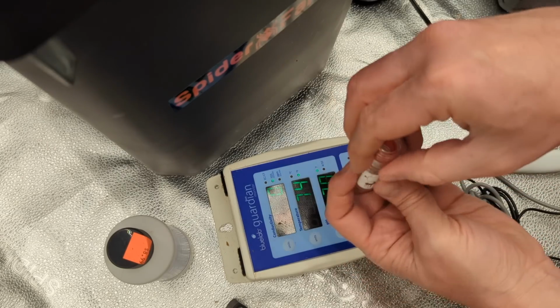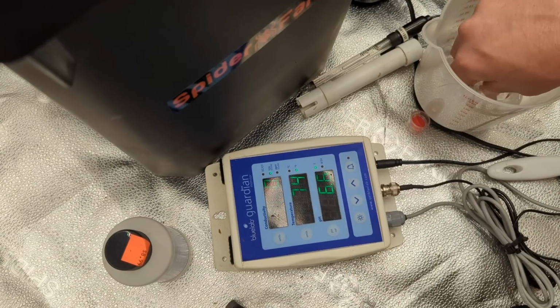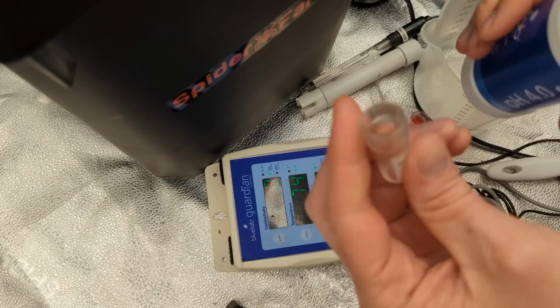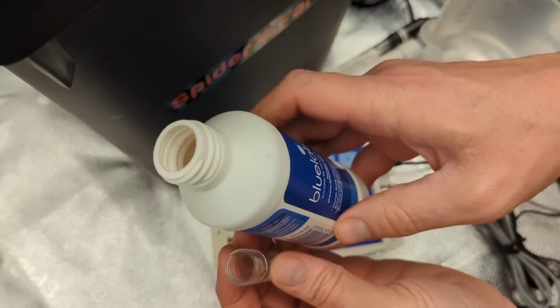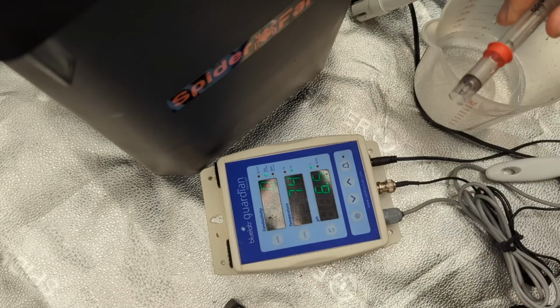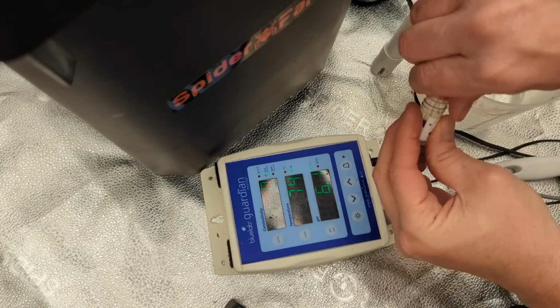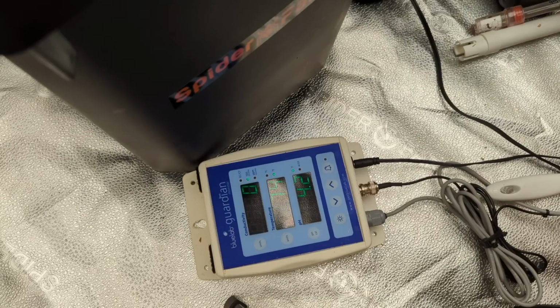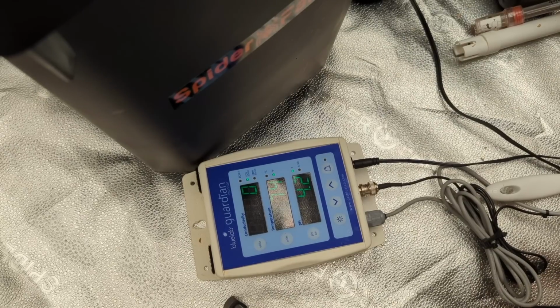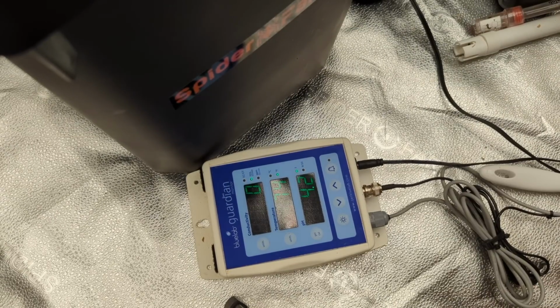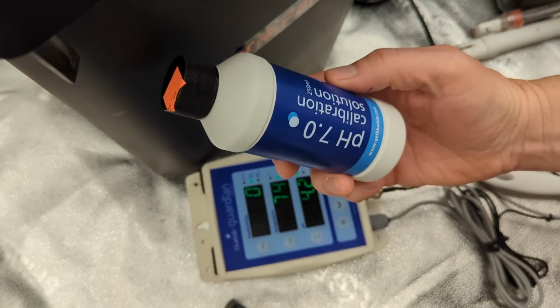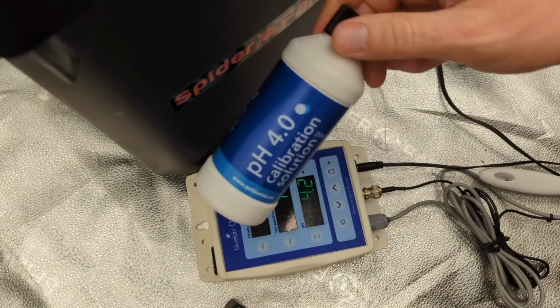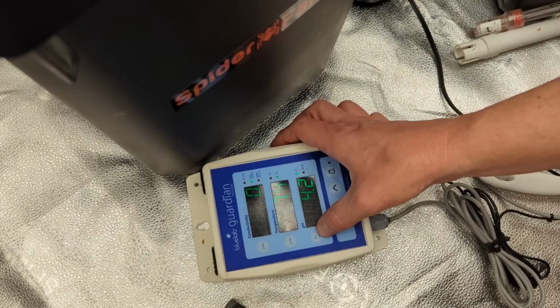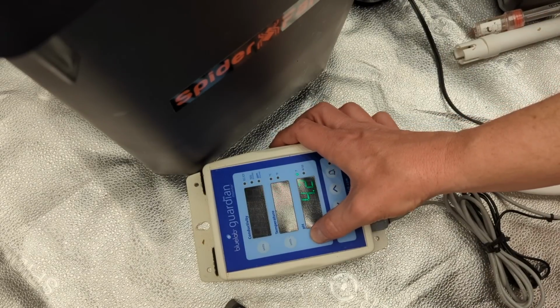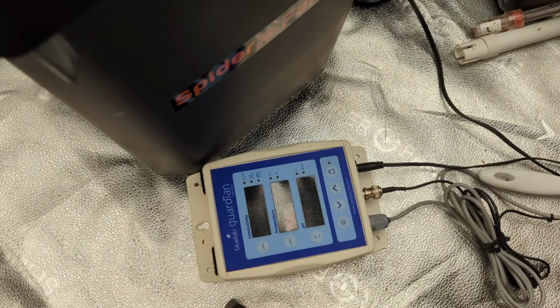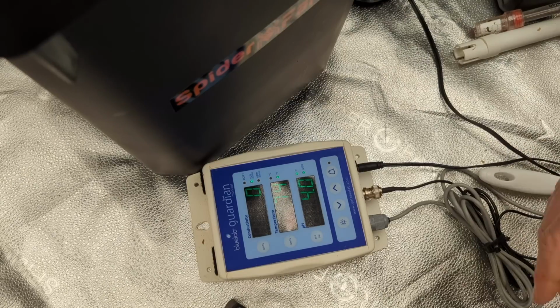We're going to empty this old stuff, rinse out the water, clean and dry it out. Take some calibration solution number 4, wipe off the probe. Take number 4 solution, press it down in. Just going to let that sit there a second and stabilize. So the 7 solution was dead nuts right here. When I put this 4 in, it was 0.2 off. We're going to hold down this pH calibration button again. There we go. Now we're calibrated for both solutions.